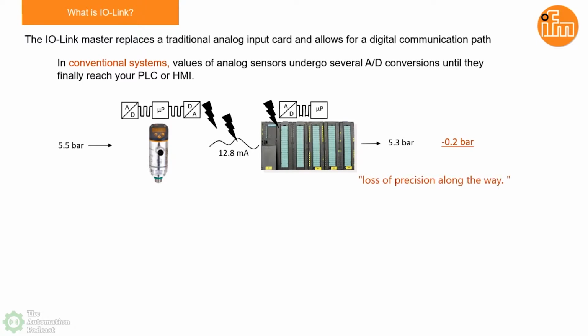In this case, you might lose 0.2 bars from that. So the true accuracy isn't simply from the sensor's specification - it's something you need to look at across the whole life cycle of the transmission itself.